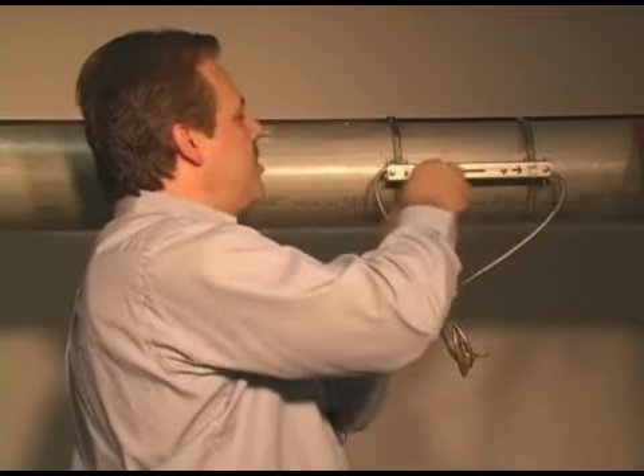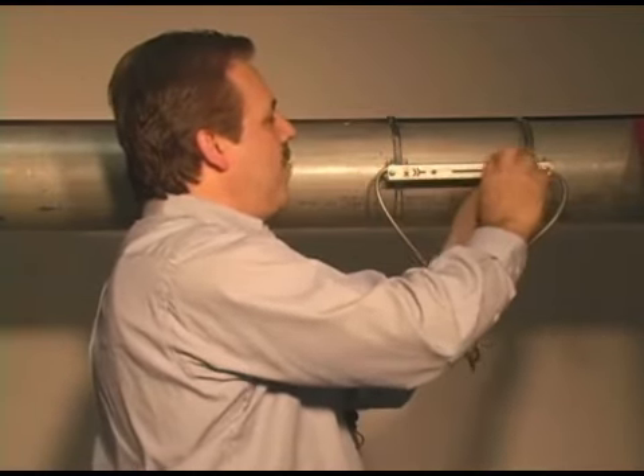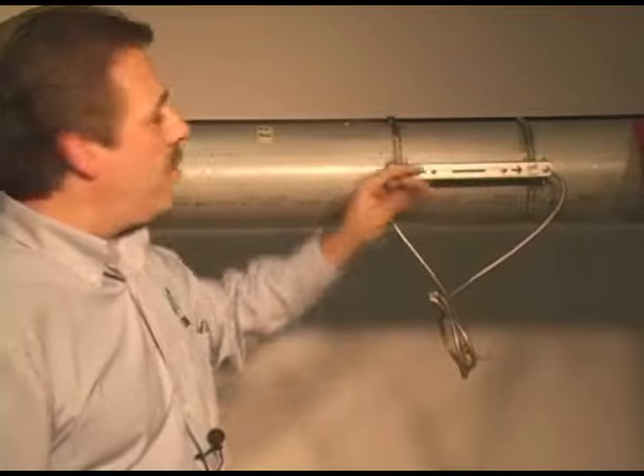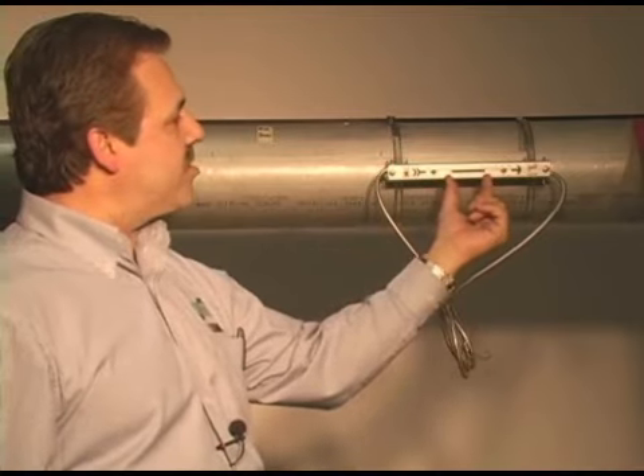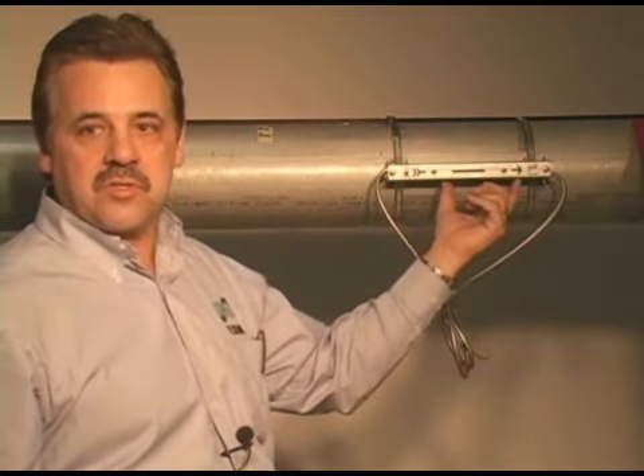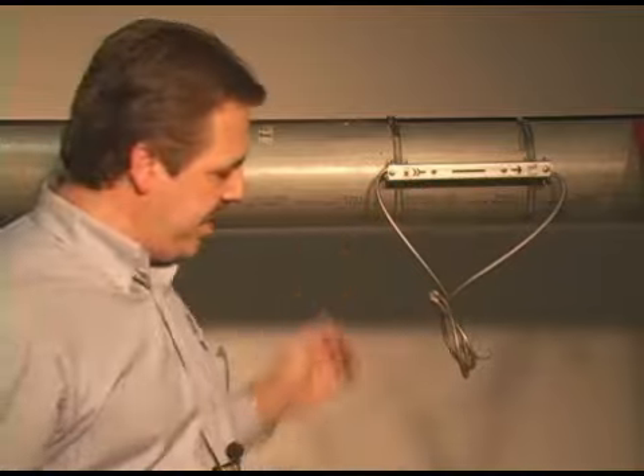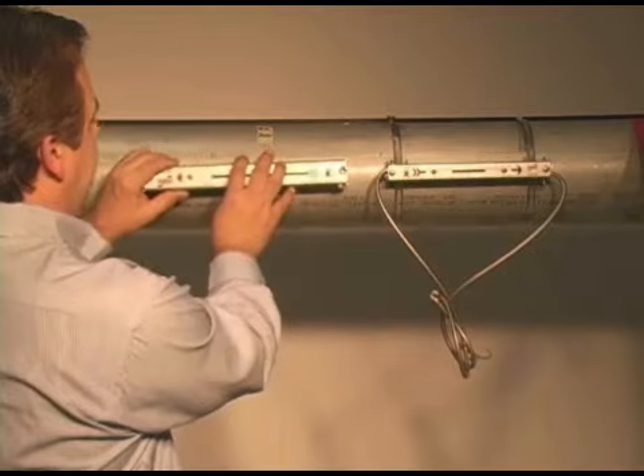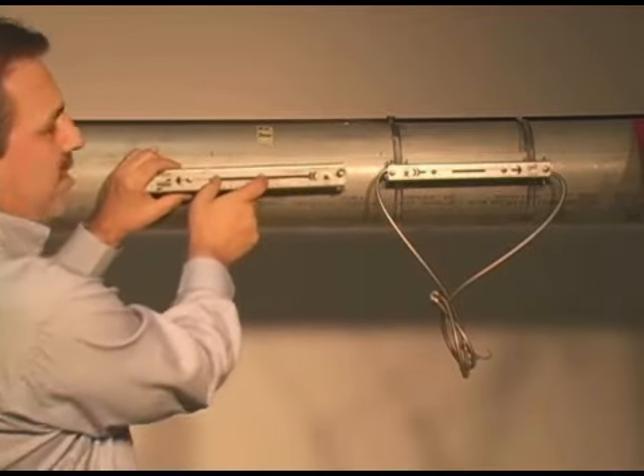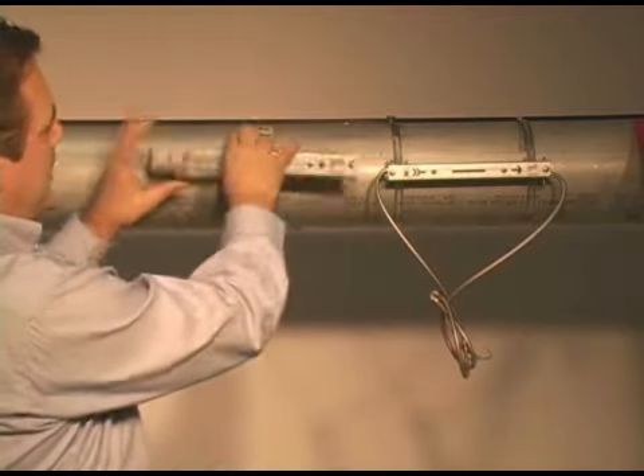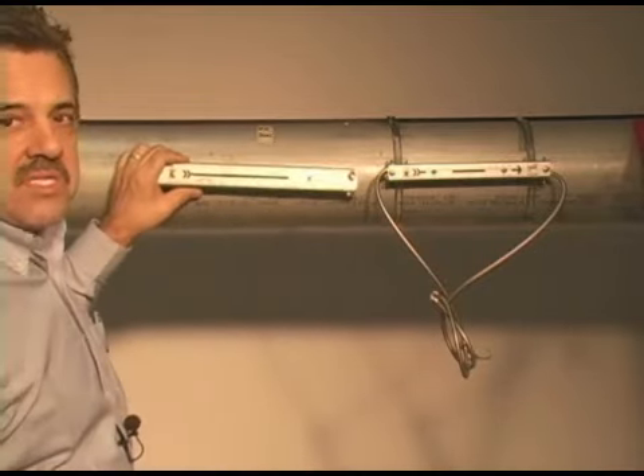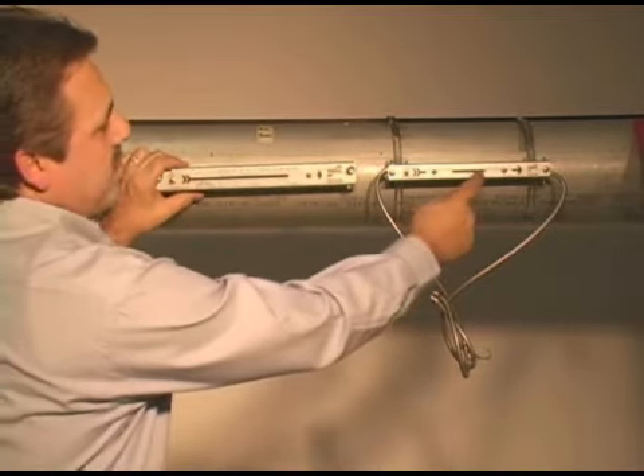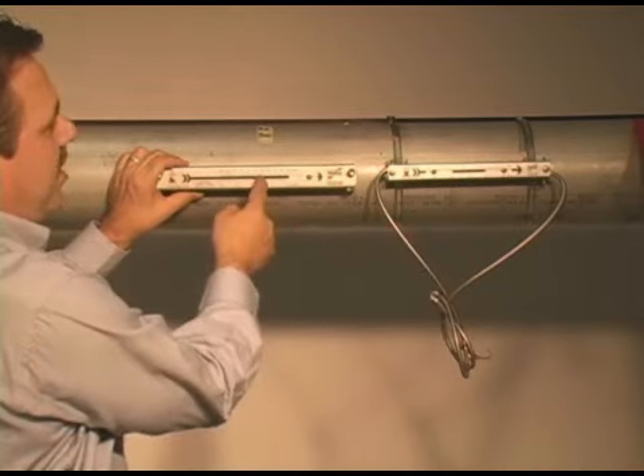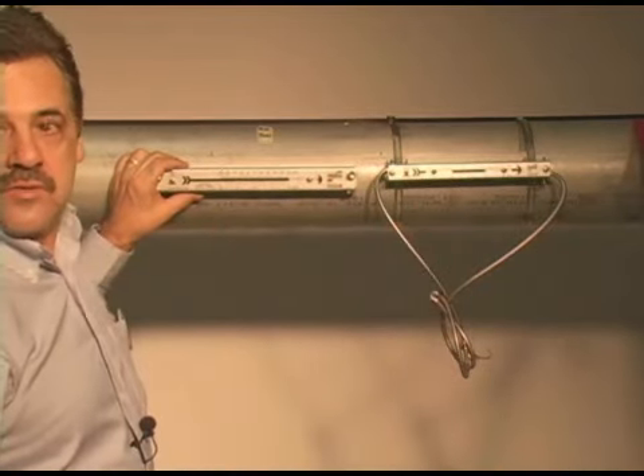Pretty simple installation. It's pretty intuitive. If you're just mounting with one track, where you have the distance to mount one track and put the two transducers into the single track, it's very easy. If you're dealing with a bigger pipe, you'll have a second track, and you'll have your transducer in the second track. Again, that's a pretty easy solution. You can measure out with a tape measure from here to here to get your spacing distance between the two.